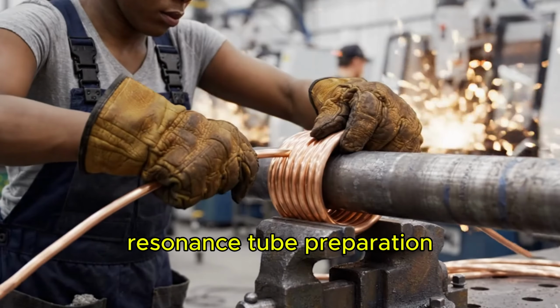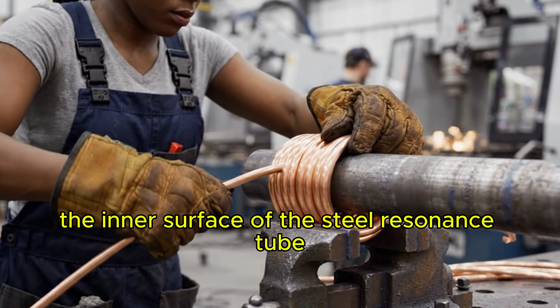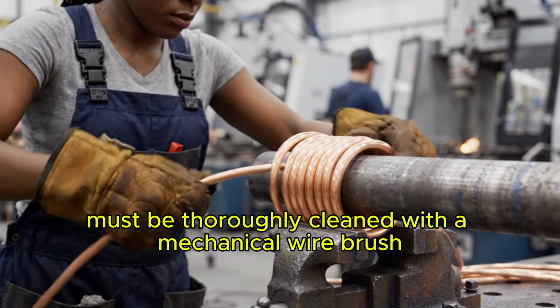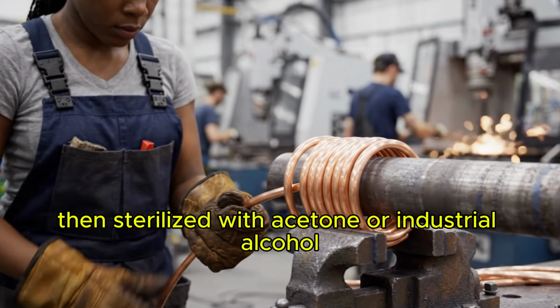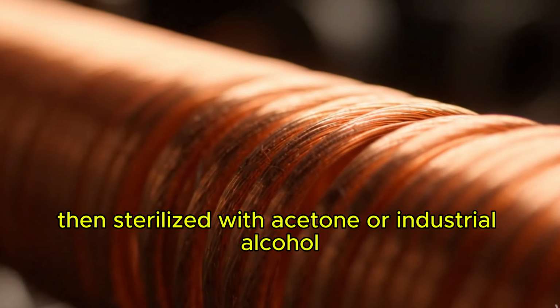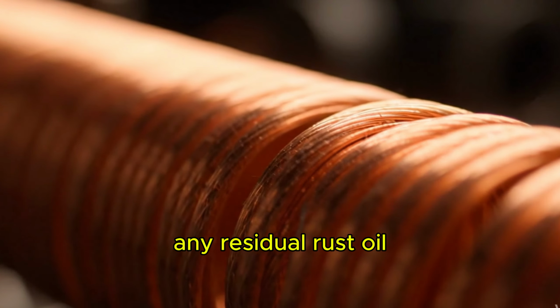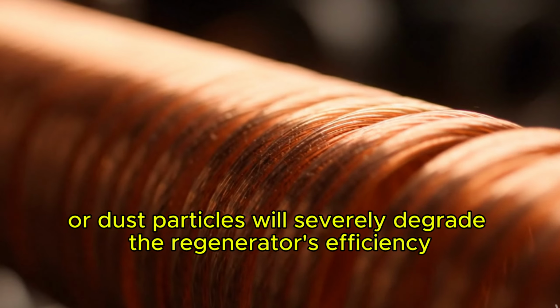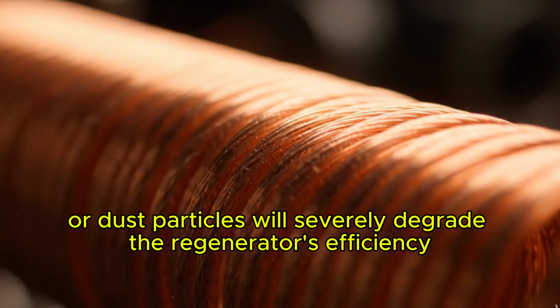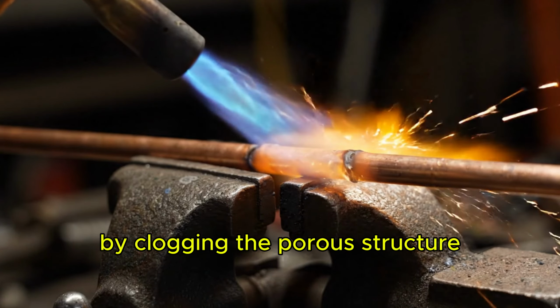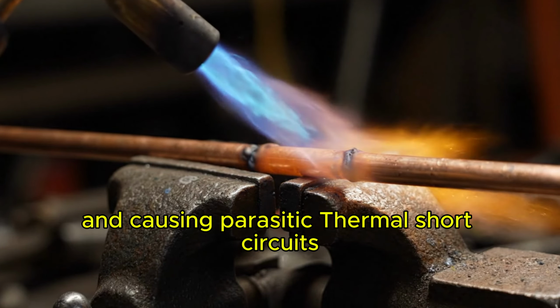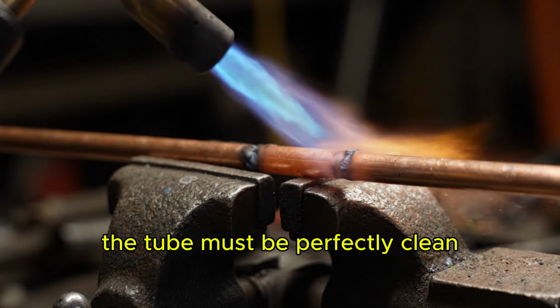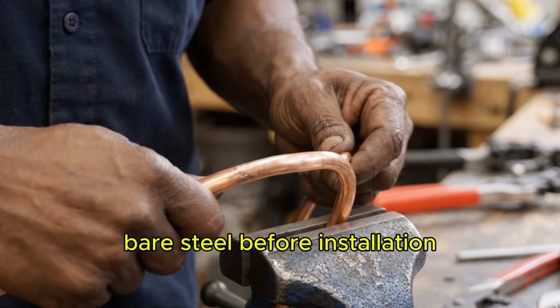Resonance tube preparation. The inner surface of the steel resonance tube must be thoroughly cleaned with a mechanical wire brush, then sterilized with acetone or industrial alcohol. Any residual rust, oil sludge, or dust particles will severely degrade the regenerator's efficiency by clogging the porous structure and causing parasitic thermal short circuits. The tube must be perfectly clean bare steel before installation.